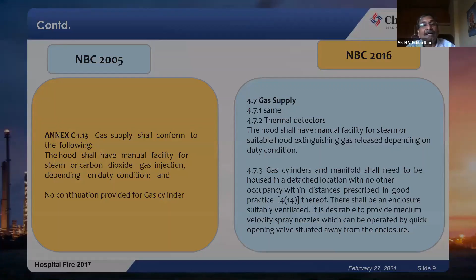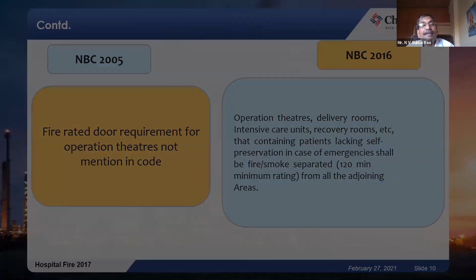Apart from that, fire rated door requirements are clearly specified in the new code. Earlier it wasn't clear whether operation theaters needed this, but in the new code it's very clear that operation theaters, delivery rooms, intensive care units, and recovery rooms all need to have a 2-hour fire rating system.